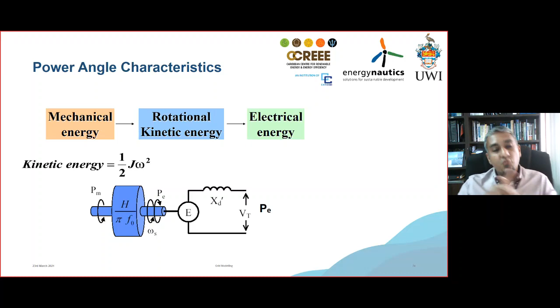So why is this important? When we look at your protection, if a fault happens, can your system regain its synchronism, or perhaps, I should say, should it not lose its synchronism? That fault needs to be cleared within a particular time frame, based on the energy that will be stored during the fault. Because when you have a fault, essentially you have disconnected your electrical load, and by disconnecting your electrical load, your mechanical energy is being pumped into the system through this generator, which will cause a change in your rotor angle.